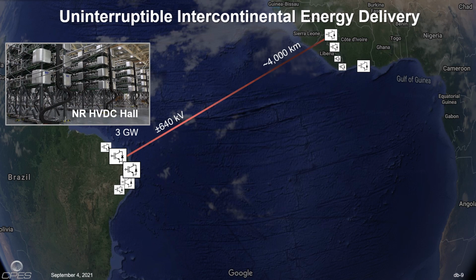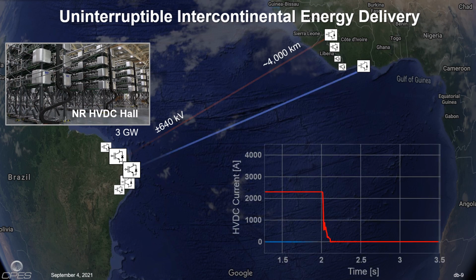To illustrate the previous point, we have simulated a situation where a 3 gigawatt, 4,000 kilometer long, undersea HVDC line connecting two continents has to be turned off for some reason, and the whole power transferred to another 3 gigawatt line. The simulation shows that transferring 2,300 amperes from one line to another can be done in less than 100 milliseconds. For uninterrupted power delivery, this huge intercontinental power transfer would require less than 100 kilowatt hours of energy storage, which is equivalent to just one Tesla car.